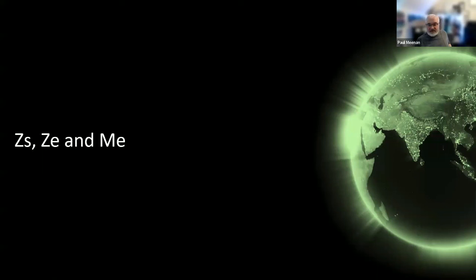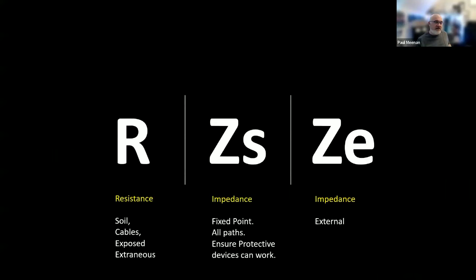Now, one of the key things for the success of earthing and bonding is ZS, ZE, and ME, which is the phrase I use. In electrical installations, again, if there are any learners on here, I break it into three concise parts: resistance, impedance, ZS, and ZE. Resistance, we look at the resistance when we're looking at earthing of the soil, of the cables, of the exposed parts, of the extraneous parts to prove safety.